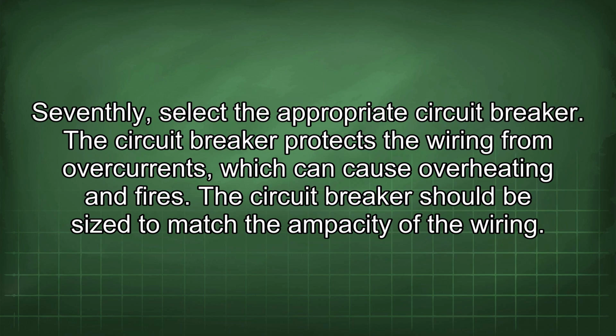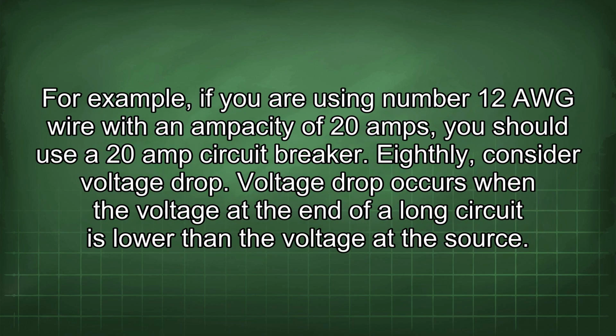Seventhly, select the appropriate circuit breaker. The circuit breaker protects the wiring from overcurrents, which can cause overheating and fires. The circuit breaker should be sized to match the ampacity of the wiring. For example, if you are using number 12 AWG wire with an ampacity of 20 amps, you should use a 20 amp circuit breaker. Eighthly, consider voltage drop.